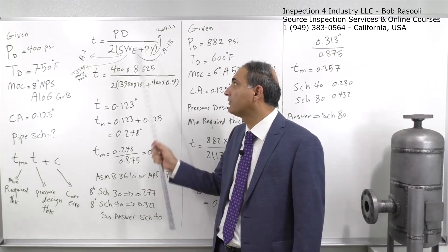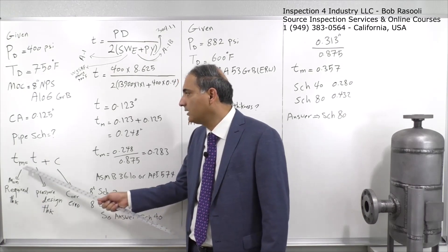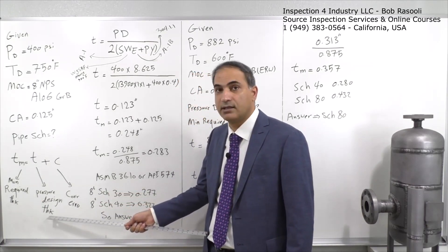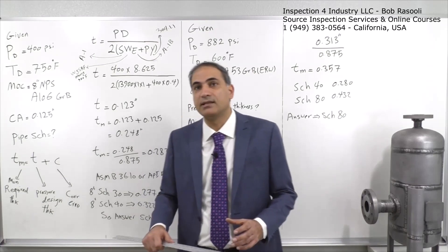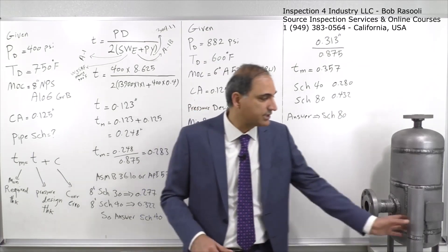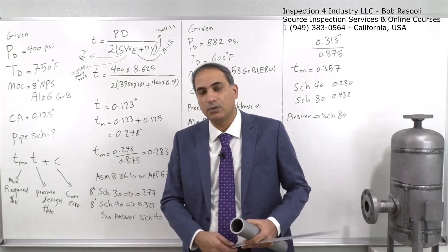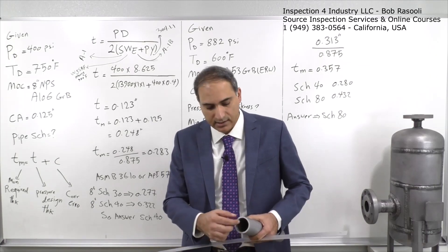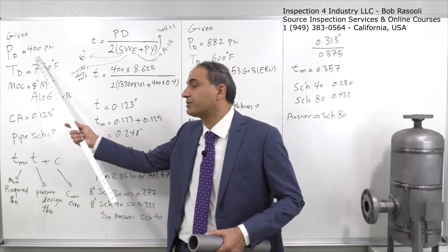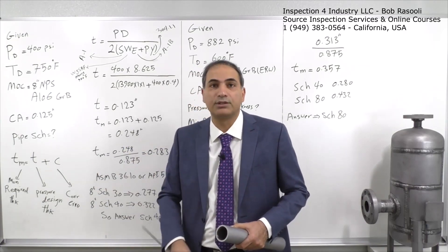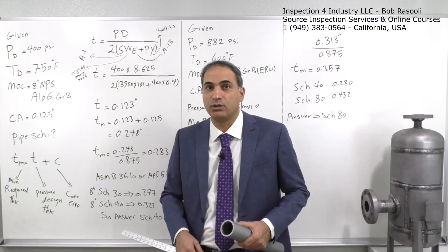ASME B31.3 Section 304.1.1 states that TM — the minimum required thickness — equals T, the pressure design thickness, plus the corrosion allowance. The pressure design thickness is the wall thickness needed purely to resist internal pressure. We want to determine what wall thickness this 8-inch pipe needs to withstand the given pressure, then add corrosion allowance to determine the required pipe schedule.